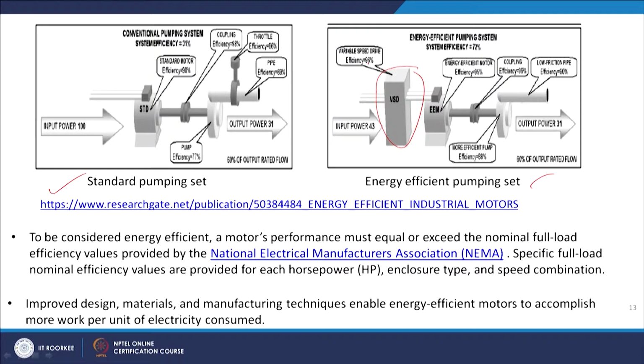What was the standard input power here, 100 units, the same amount of work we can get here by using 43 units, the output is the same, and this is made possible by changes in the units which are used for the operation of this motor. So, important is a variable speed drive if it is used. It is 99% efficient.